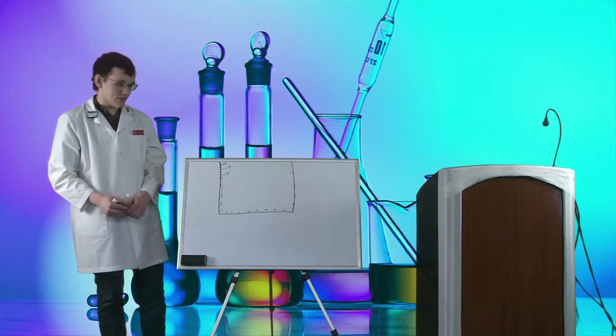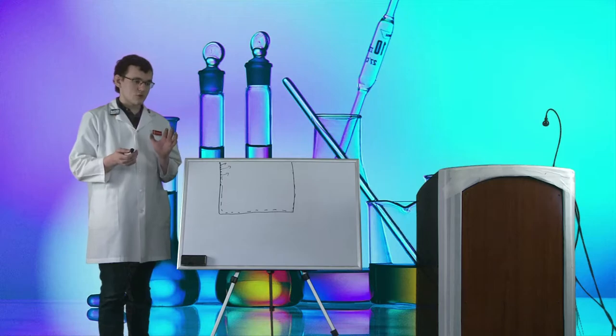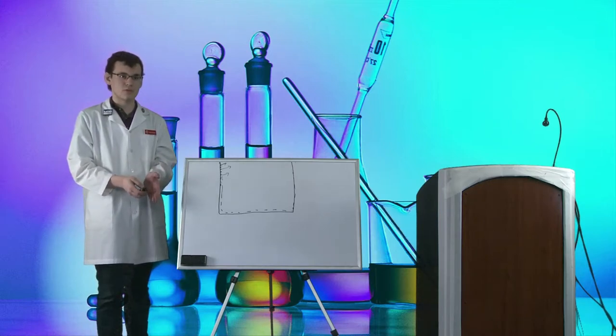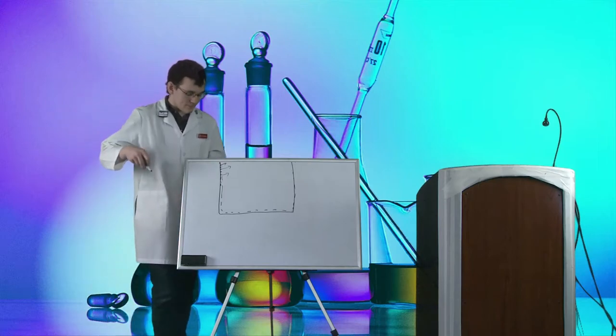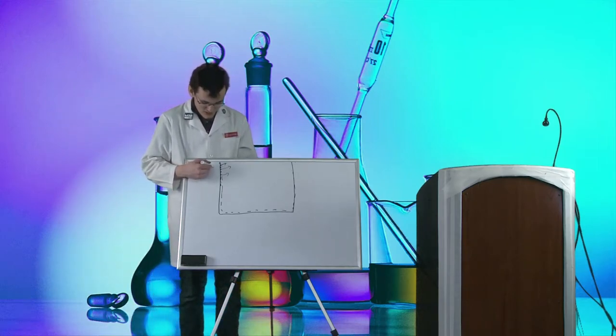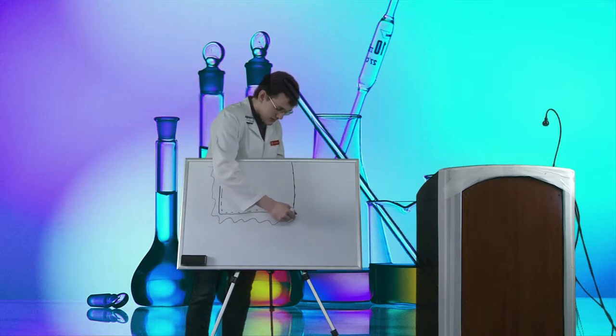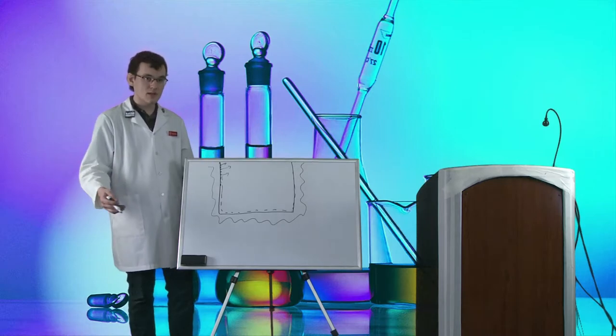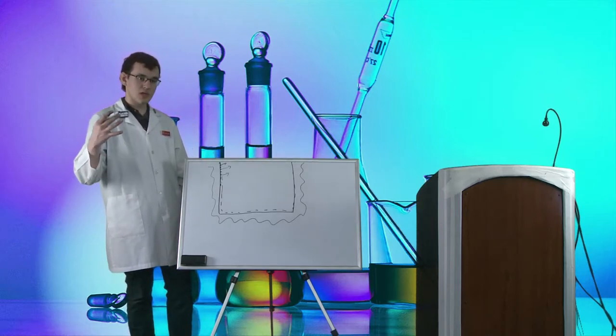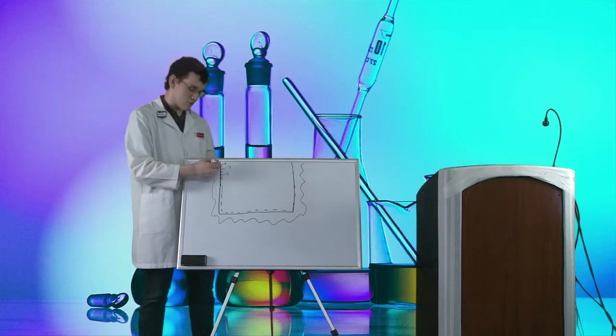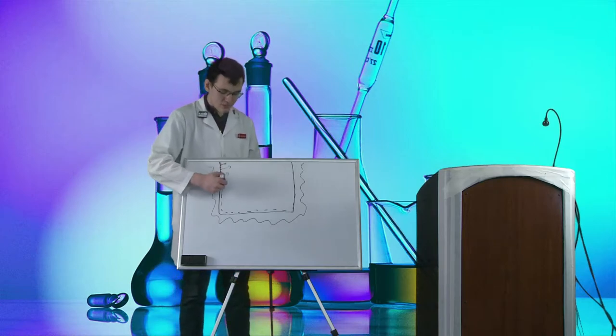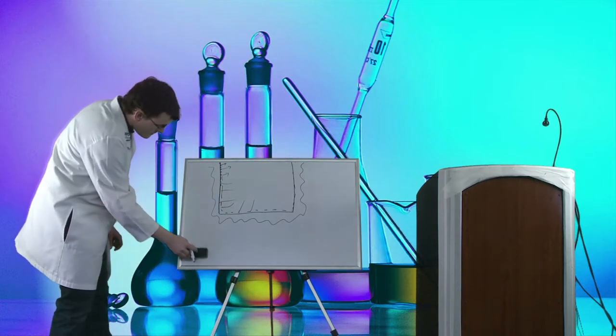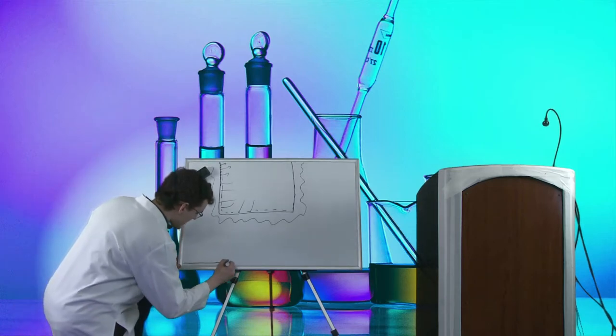The pump-down curve goes all the way to ultra-high vacuum range for some systems, but for our reactor and SEM it pretty much stops in the high vacuum range because we only have a rotary pump and a molecular pump — no ion pumps. For any bigger system, you'll use those. We do have a cold trap — another type of getter pump — though we don't use it very often because we don't need to.